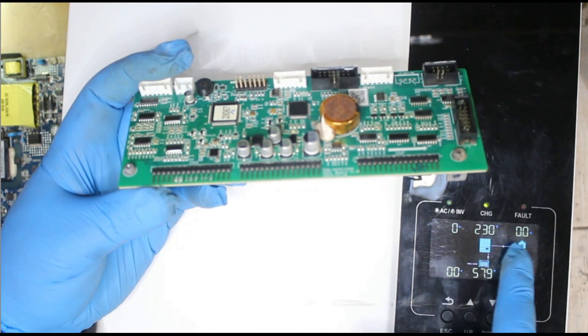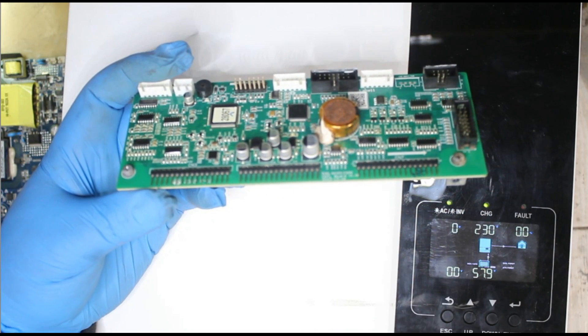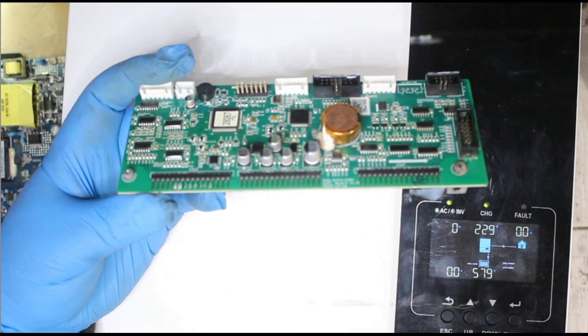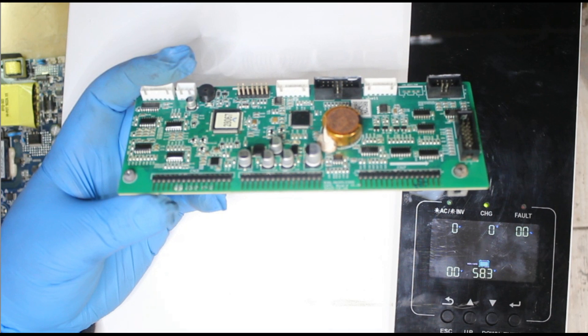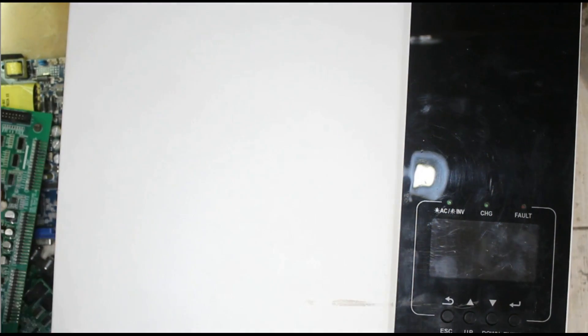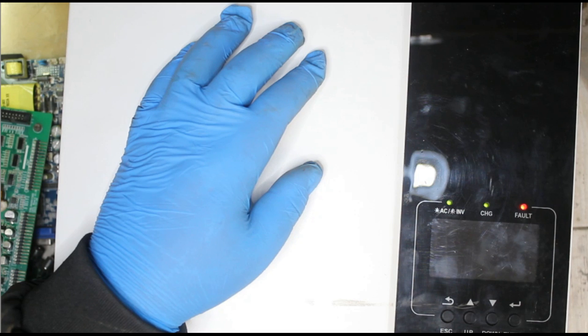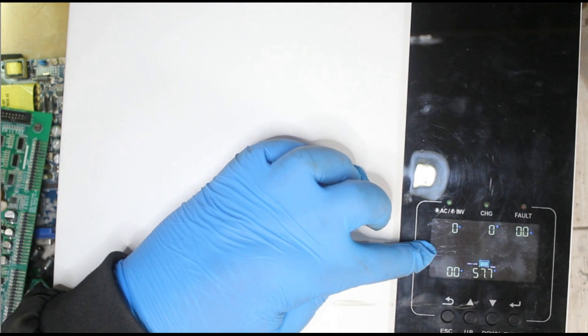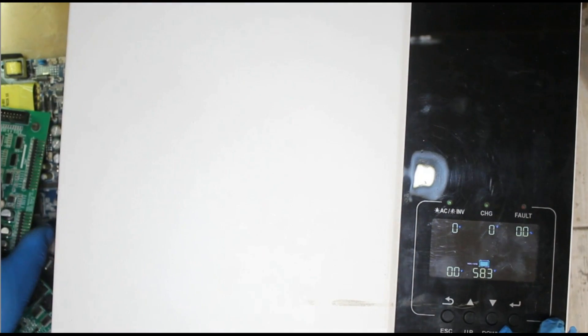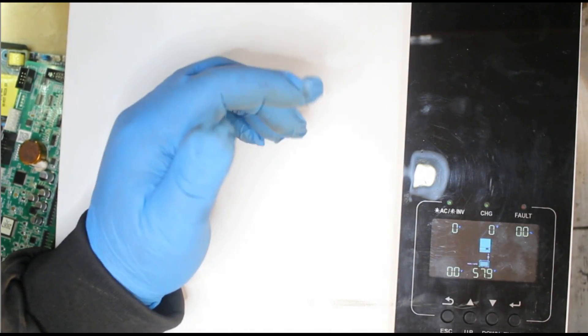Thank you very much. You can see now the inverter has no alarm. Battery voltage is okay. I'm going to test all other functions but so far it looks good - the errors that the inverter came with are gone and it's even faster to switch on. Let's switch off and on again. You saw when it started it showed 888 for a long time before - now it only shows for one second then it's on the inverter screen. The inverter is okay now - we've sorted it. Hope you liked the video, thank you very much for watching and I hope to see you on the next video.